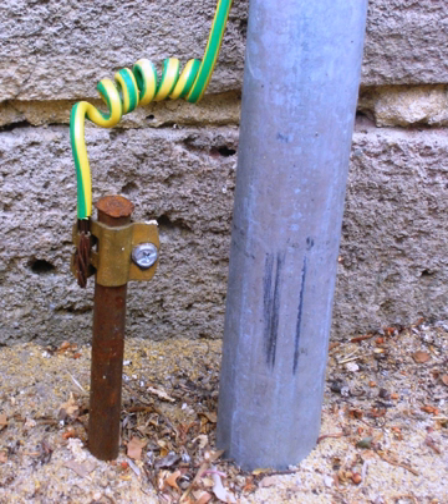See single-wire earth return. For measurement purposes, the earth serves as a reasonably constant potential reference against which other potentials can be measured. An electrical ground system should have an appropriate current carrying capability to serve as an adequate zero voltage reference level. In electronic circuit theory, a ground is usually idealized as an infinite source or sink for charge, which can absorb an unlimited amount of current without changing its potential. Where a real ground connection has a significant resistance, the approximation of zero potential is no longer valid. Stray voltages or earth potential rise effects will occur, which may create noise in signals or, if large enough, will produce an electric shock hazard.